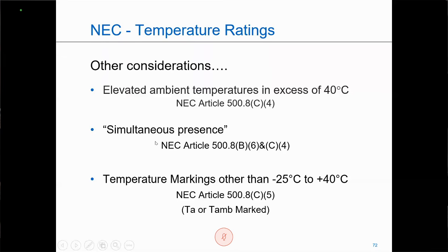Simultaneous presence. When you see a unit that says Class 1 and Class 2, that means it's good for either Class 1 or Class 2. But if I have an area where the gases and dusts are present together, then I need the unit to be rated simultaneous presence, because again, that particular fixture with dust coating on it is going to be affected as far as its gas temperature rating. It's like putting a winter coat on it. And this is the temperature markings that I had mentioned earlier that had to have the TA or the TAMB if it's outside of these, and then note those particular operating temperatures outside of this range.